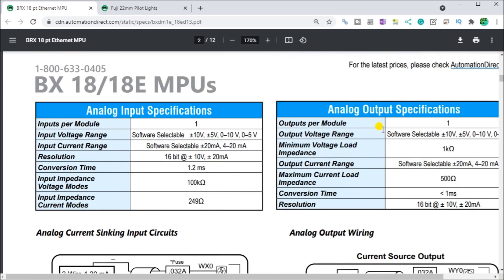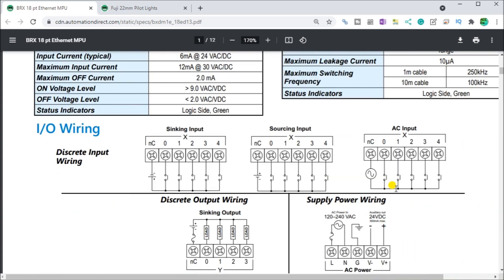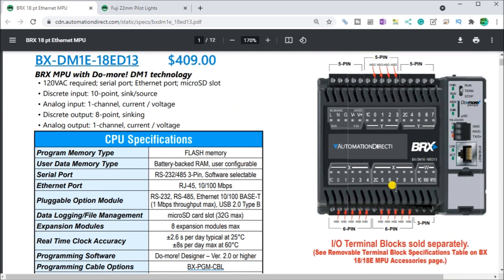Our analog output module has one output, and the output is actually scalable for all these different voltage ranges. The minimum voltage load impedance is one kilo ohm, and our maximum current load impedance is 500 ohms. That ensures our analog signal pushed through that output is properly restricted. That covers the analog output wiring and the specifications of our PLC.